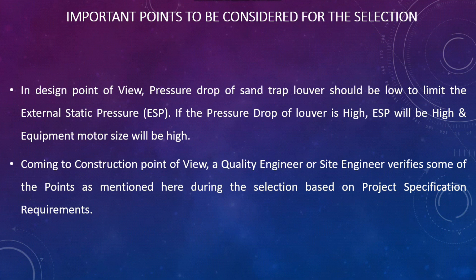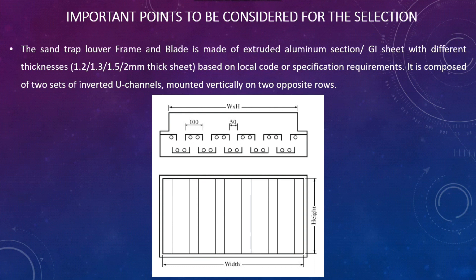Coming to the construction point of view, a quality engineer or site engineer verifies some of the points as mentioned here during the selection, based on the project specification. The sand trap louver frame and blade is made of extruded aluminum section or GI sheet with different thicknesses like 1.2, 1.3, 1.5, or 2mm thick sheet, based on the local code or specification requirement.